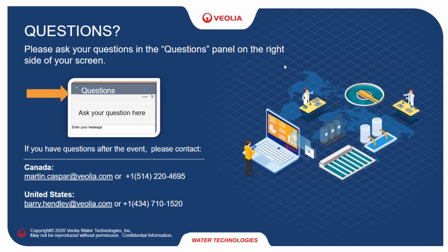But maybe Brian or Mark do, because I can't speak to that myself, but I know that yes, they do. Yes, and I know over in the States we have several plants that use the streaming current. It helps them reduce coagulant dosage, keeps them from overdosing. So yeah, it's a great optimization tool.